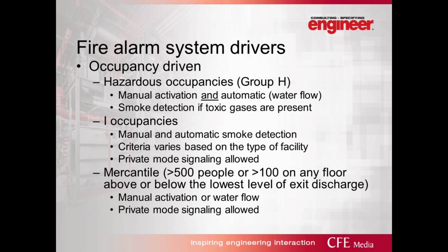as well. Now, there are exceptions in the code as to where those devices are required to be located. So generally, in a detention center, you're not going to put manual fire alarm boxes throughout the housing areas, for instance. Those are going to be in a controlled location for staff utilization. We're also able to use the concept of private mode signaling in I occupancy. What that is talking about is the ability to notify the staff members that are trained to take action.